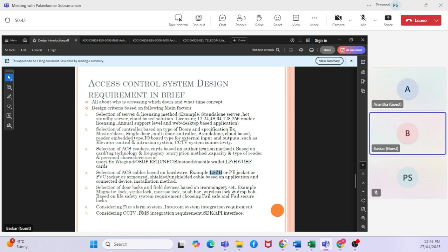The fire alarm system is also a very crucial part - integration with the fire alarm system. Some doors are fail-safe and fail-secure. In case of any fire, there should be doors to evacuate, and some doors should remain secured. It has to be configured so that the secure door is not accessible to anyone during fire conditions.